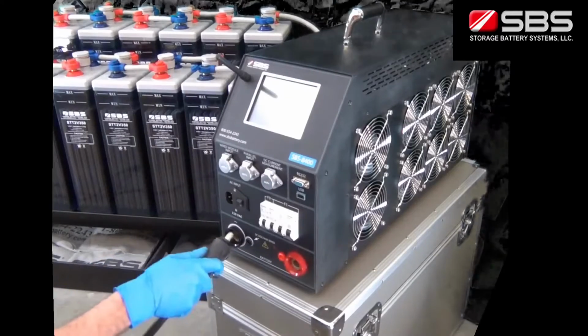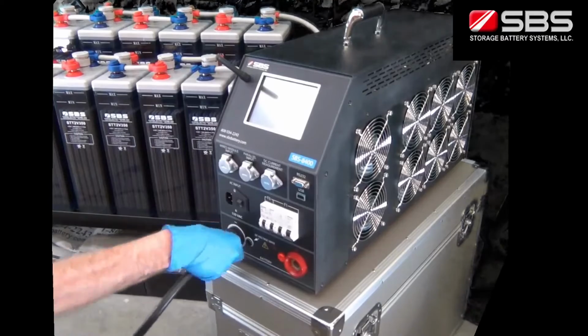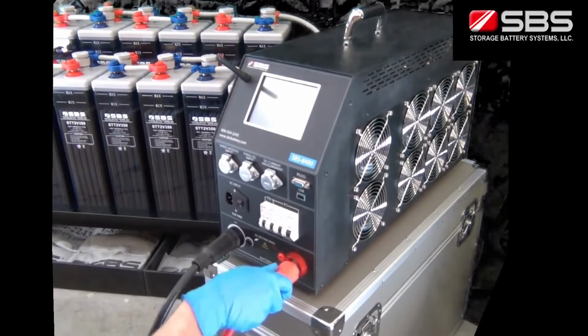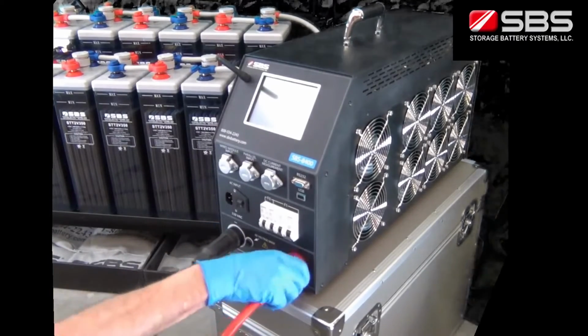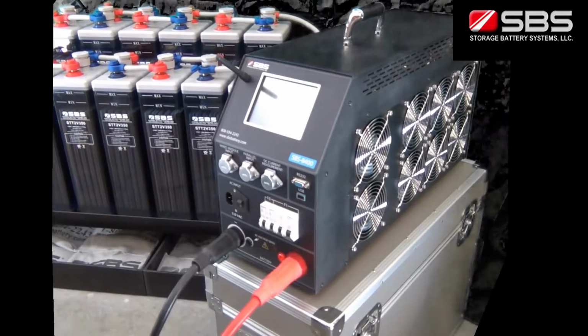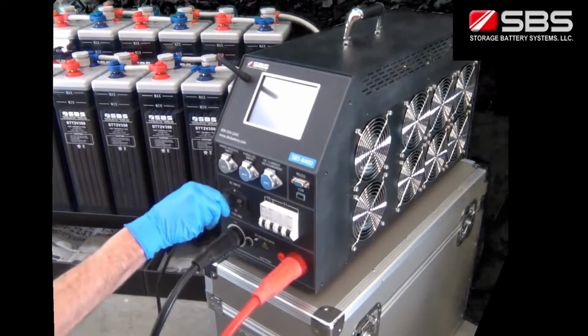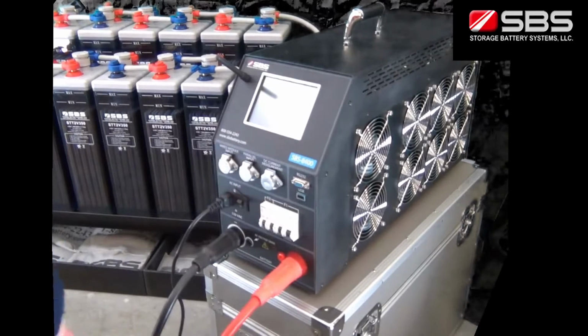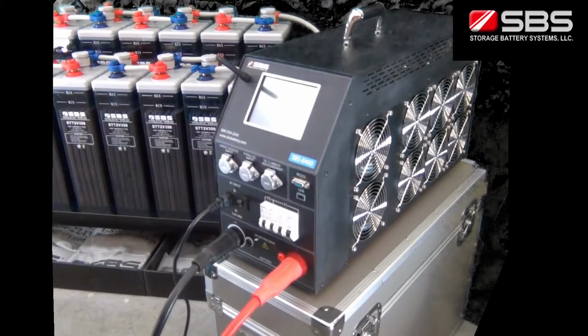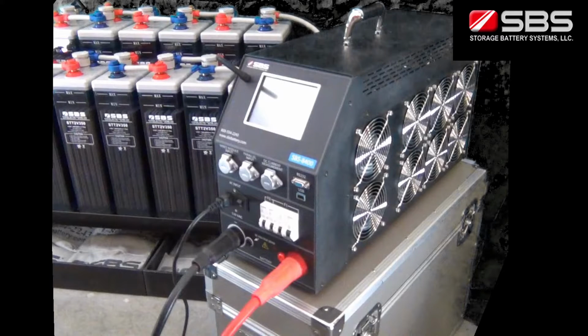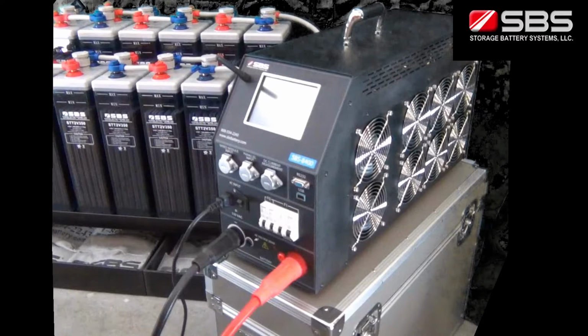analysis. Prior to turning on the SBS-8400, it is necessary to make all of the main machine connections. First, connect the red positive and black negative cables to the power connectors and bolt the test cables onto the main positive and negative of the battery string to be tested. Use the alligator clips to connect the data collection modules to the batteries. Refer to the user manual to follow the proper module connection. Now that all the main connections have been made, we can start up the SBS-8400 by turning on the AC power switch on the front of the unit.